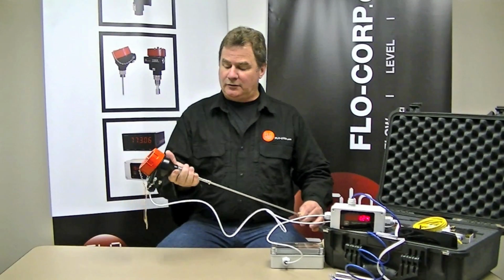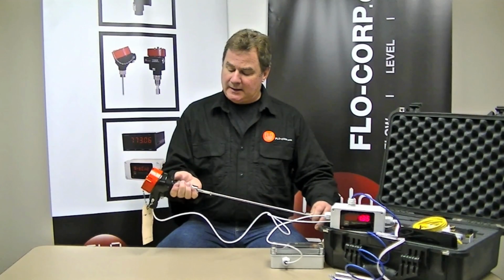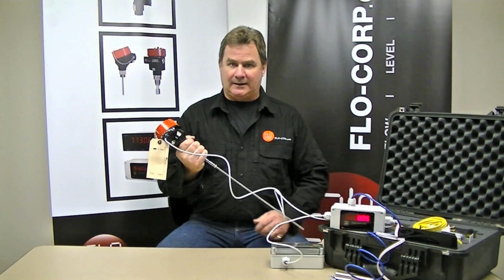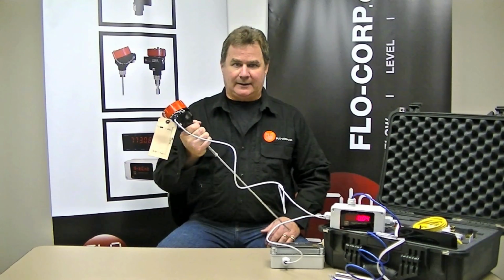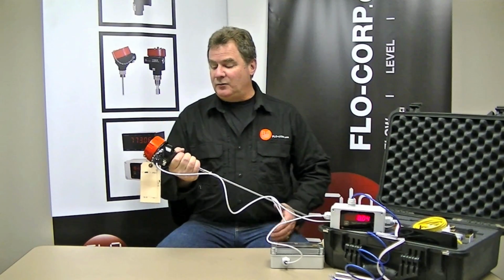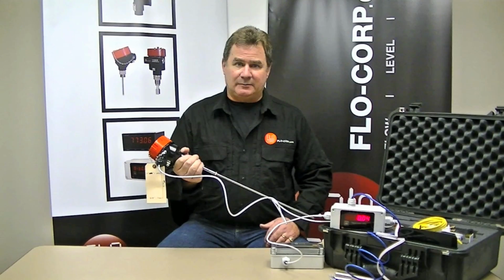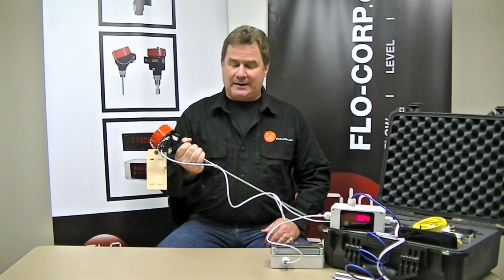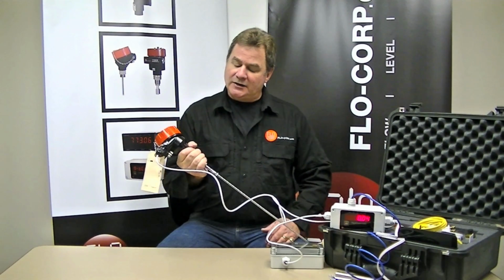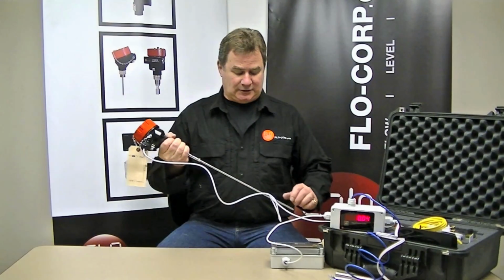The first thing you want to do is hold the process connection in one hand, thereby grounding the transmitter to you. It could operate in a non-grounded system as well. It's just that this tracer has been calibrated for a grounded system, so I need to hold the process connection.